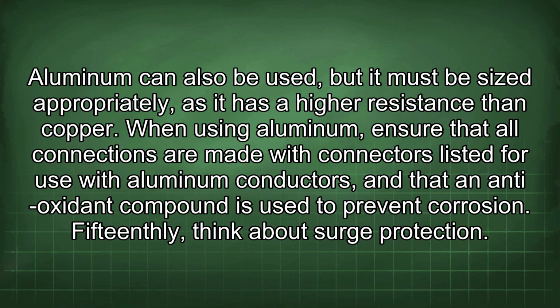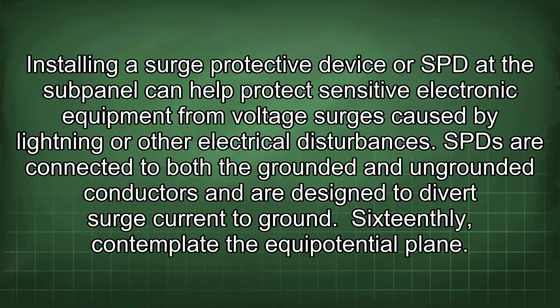15thly, think about surge protection. Installing a surge protective device or SPD at the subpanel can help protect sensitive electronic equipment from voltage surges caused by lightning or other electrical disturbances. SPDs are connected to both the grounded and ungrounded conductors and are designed to divert surge current to ground.